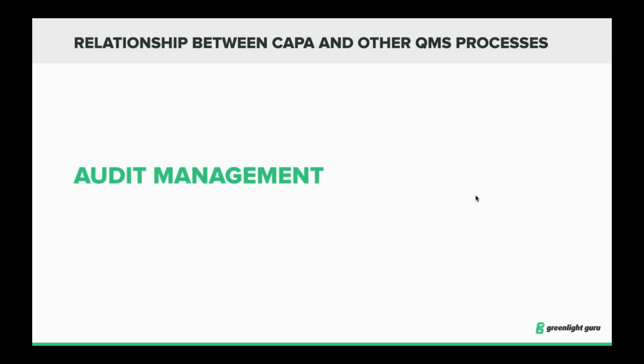Now, if there are bigger issues, of course, absolutely consider a CAPA. And I've seen some companies differentiate their practices for internal audit findings versus external audit findings. Like if you get an FDA 483 observation or an ISO observation, that might automatically warrant a CAPA investigation. And this is a little bit of a preference thing. Again, I keep going back to thinking of CAPA as more systemic-issue based. If it's something that I can address using another process that I've defined, like change management or training or what have you, then leverage those workflows and details within those particular procedures.